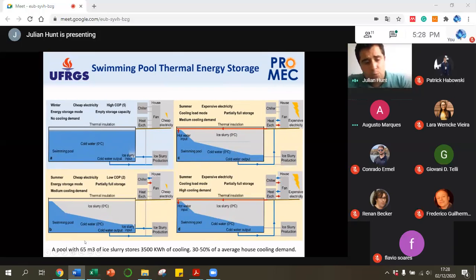An average pool, with around 65 cubic meters of ice slurry storage capacity, can store 3.5 megawatt hours of cooling, around 30 to 50% of average house cooling demand. You wouldn't use this in a shared apartment building where people want to use the pool, but this is for a house where people don't want to use it, so the pool becomes a storage tank.